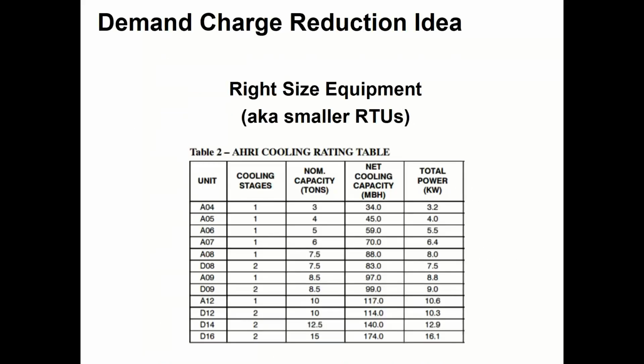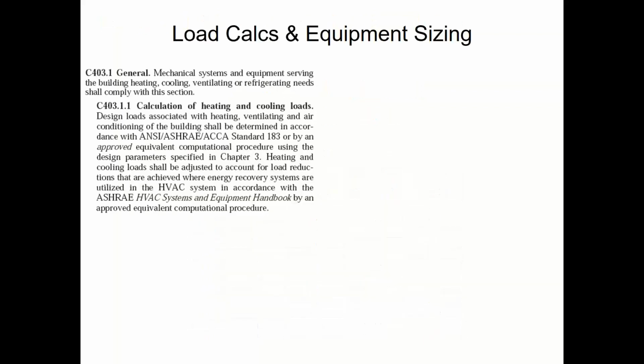In regards to demand charges we talked about earlier, just to give you an example on here, if I was to put in a 10-ton unit, so let's just look over here. Let's say I looked at A12 on here, 10 tons. It is 10.6 kW is my draw when that thing's on. If I was to replace that with a 7.5 ton, it is 8 kW draw. So it goes from 10.6 to 8, 2.6 kW less. Doesn't sound like a lot. If I'm doing that on all my equipment, it starts becoming a cumulative effect, and it can affect the demand charges on my building.